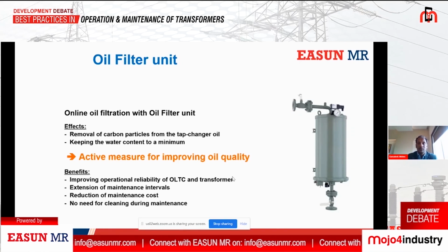Why you need to use this? Because once you are using, let us say you are having 30,000 maintenance-free operations for a tap changer, after that you have to do maintenance. If you are using this oil filter unit, it will be more or less double. So after 60,000 or 70,000 operations only you need to do maintenance. So it is not too costly. It is very much affordable.